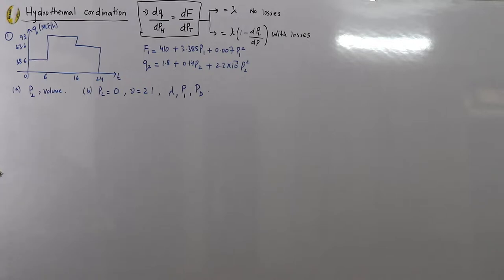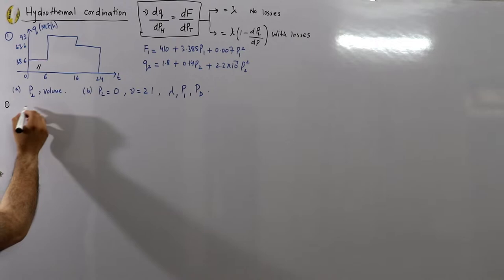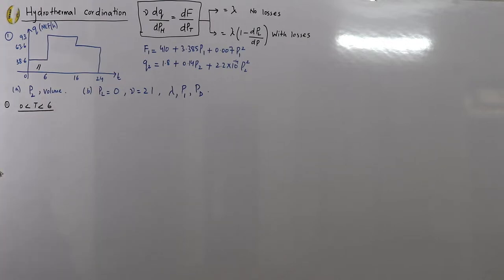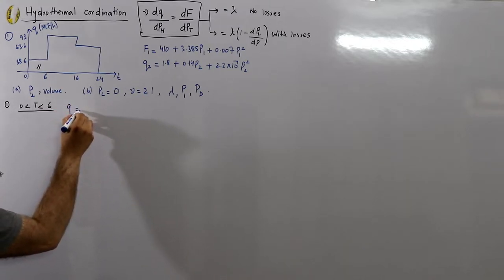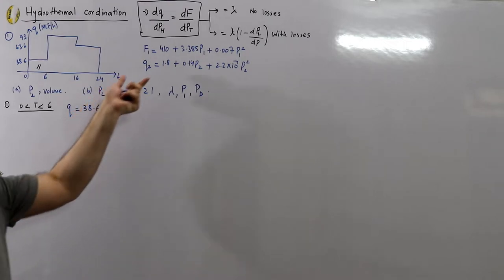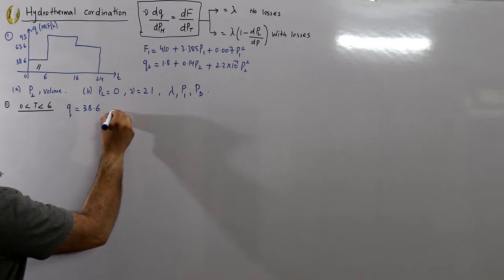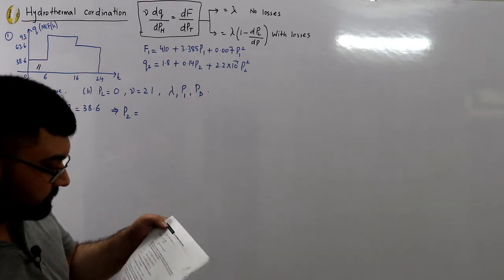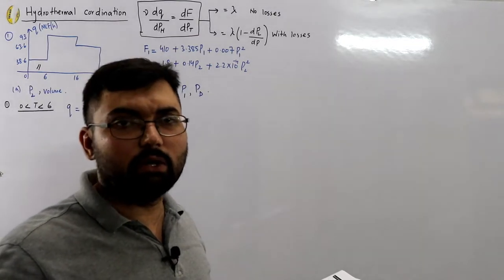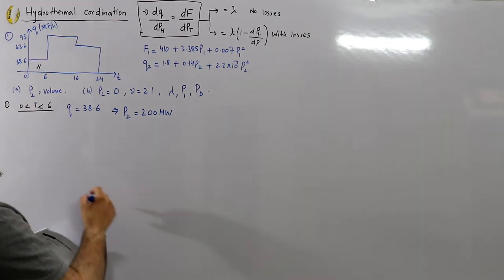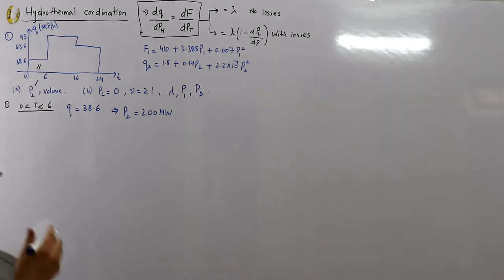For Interval 1 (0 to 6 hours), the discharge is 38.6 million cubic feet per hour. Substituting this into the discharge equation q2 = 1.8 + 0.14·P2 + 2.2×10⁻⁴·P2² gives a quadratic equation in P2. Solving and neglecting the negative root, P2 comes out to be 200 megawatts.